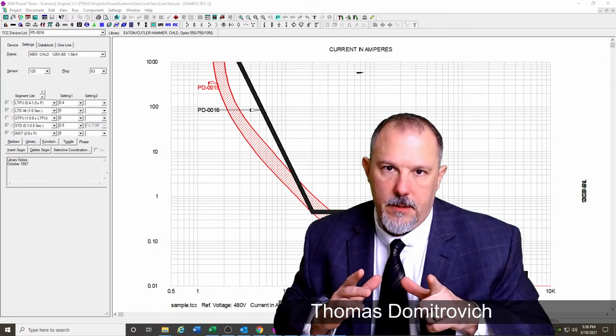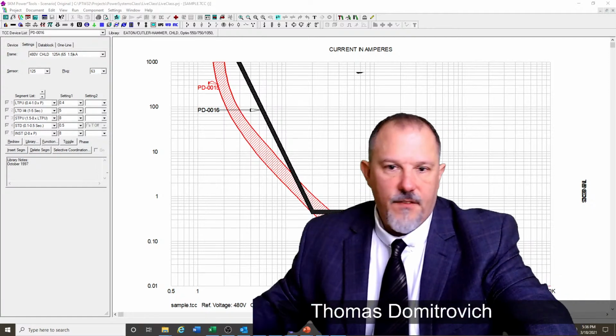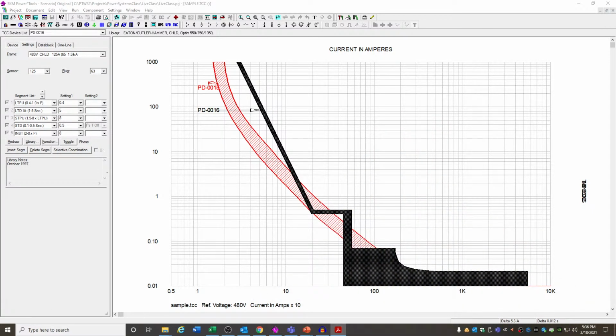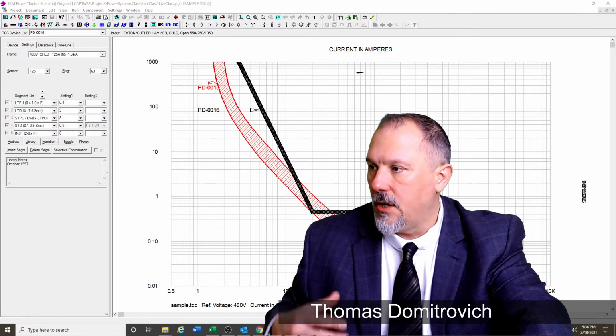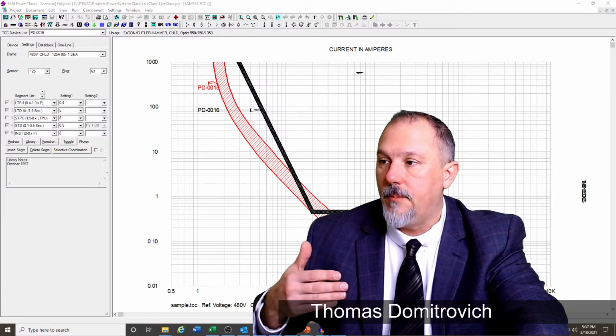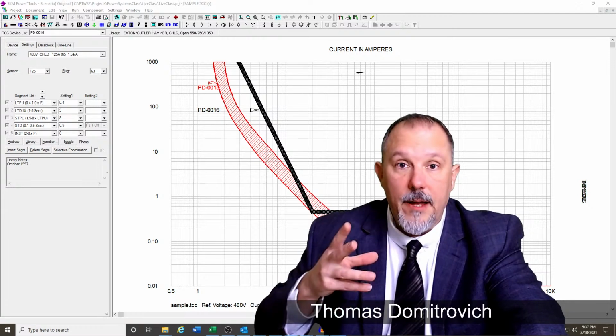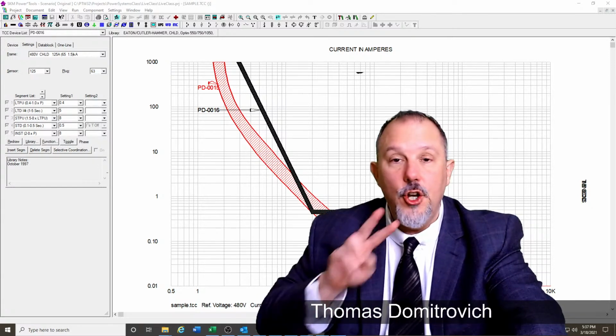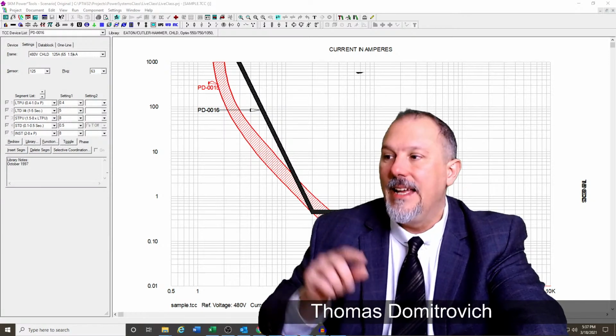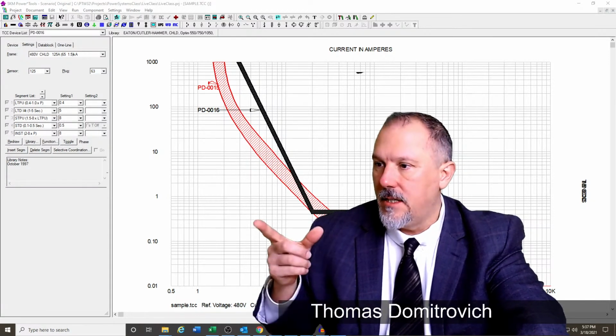Remember, when I say pickup, it is a current value. Because why? If you look at these trip curves, across the bottom is current, and up the side is time. So pickup is what level of current will I pick up, right? Will the breaker recognize that I'm going to start to open? So instantaneous pickup is defined as the nominal value of current at which an adjustable circuit breaker is set to trip instantaneously. Instantaneous trip is a qualifying term indicating that no delay is purposely introduced in the tripping action of the circuit breaker. And this is adapted from the NEC.